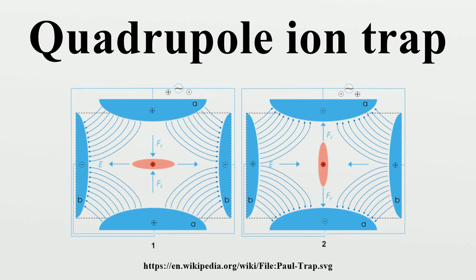There are two main classes of traps, depending on whether the oscillating field provides confinement in three or two dimensions. In the two-dimension case, confinement in the third direction is provided by static electric fields. The 3D trap itself generally consists of two hyperbolic metal electrodes with their foci facing each other and a hyperbolic ring electrode halfway between the other two electrodes.